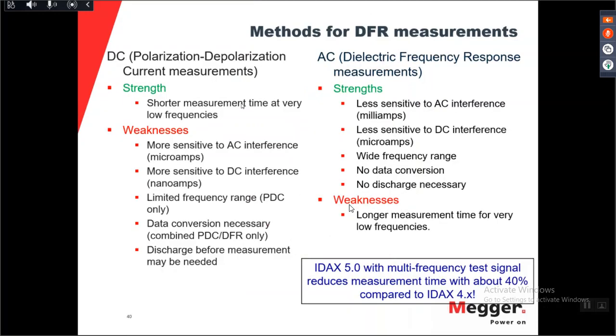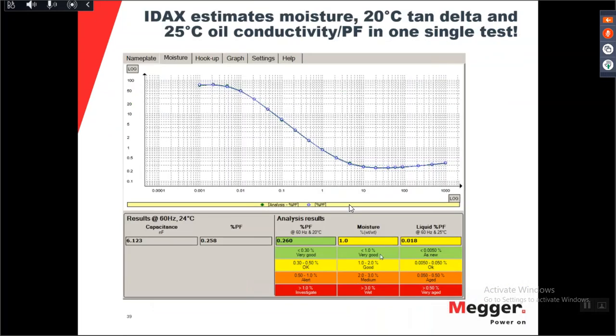The recommended action depends on when you measure. Here we can see two criteria. When you look at the standards, they say a new transformer should have less than 0.5% moisture content. But when we look at a service aged transformer, when you come above 3%, we say it's wet and it's critical. But when we look at the different standards, some actually say that more than 2% is not accepted.